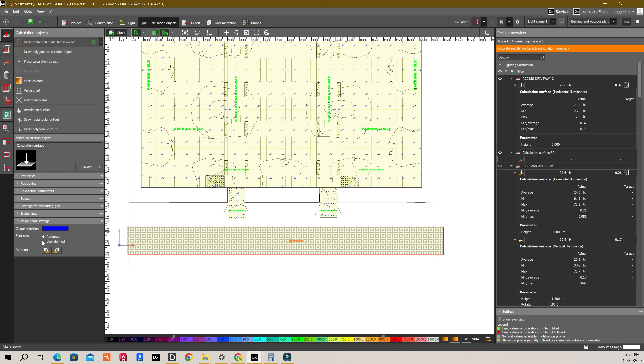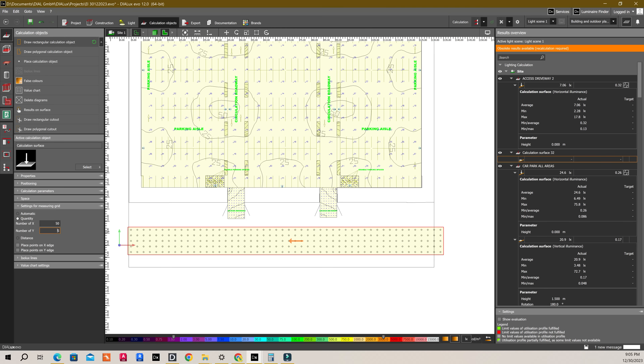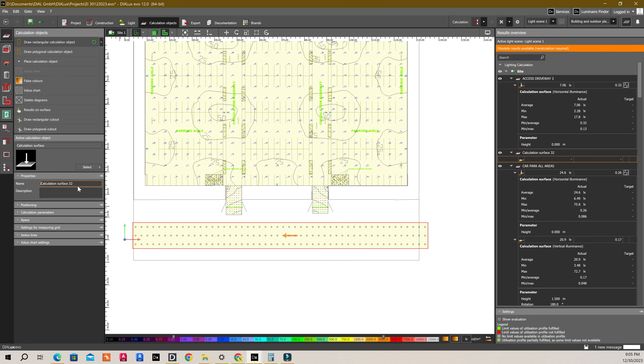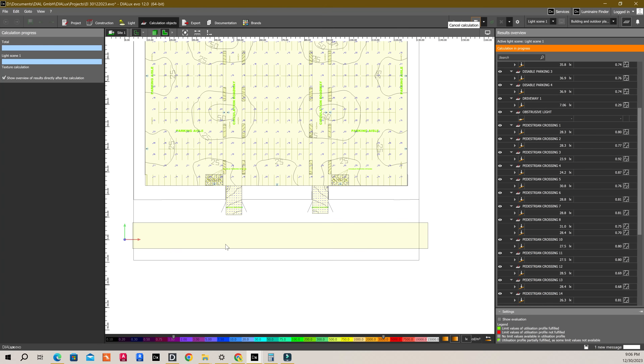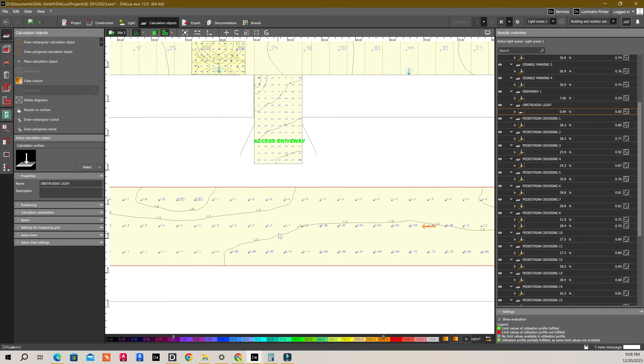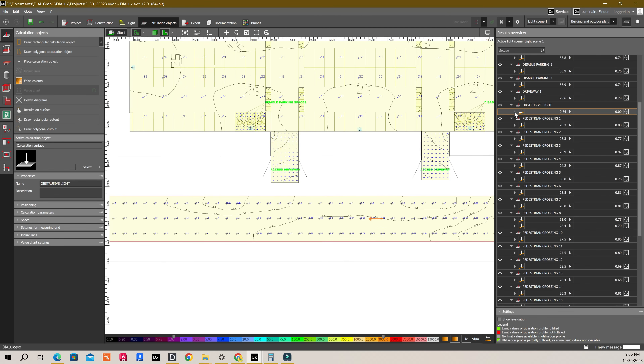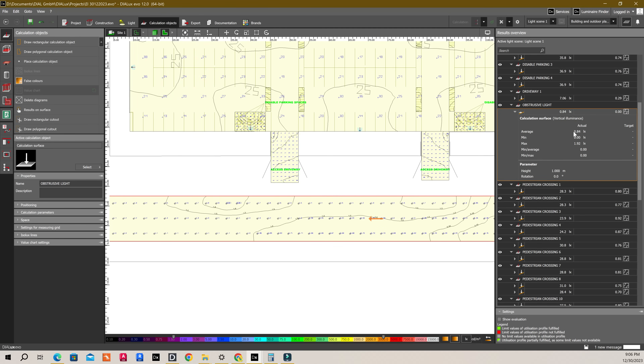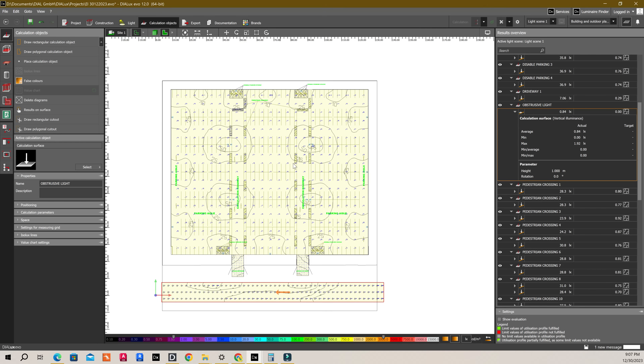I am going to draw one more rectangular calculation object here on the road to check if there is any spill light from the car park onto this road. Make sure your average values are not greater than 3. I checked the average for this area including a vertical lux calculation, and you can see the average is not greater than 1 — it is around 0.8 something. So that is fine as well.